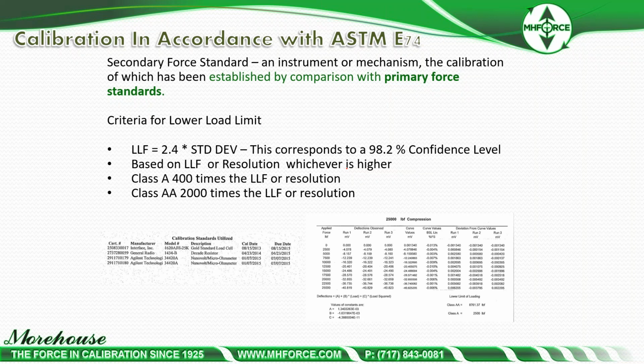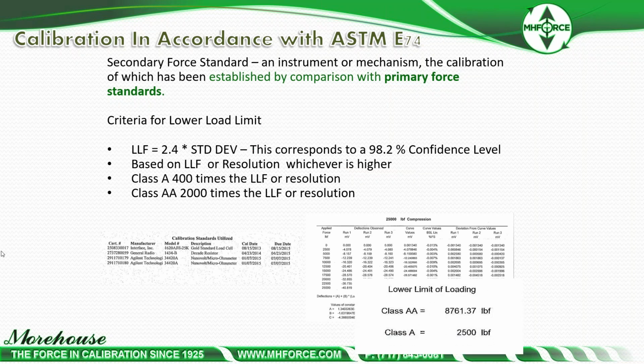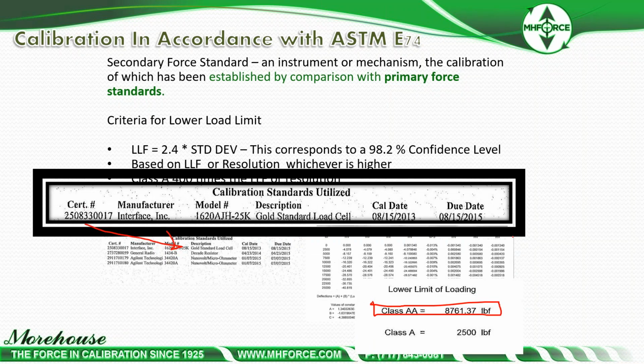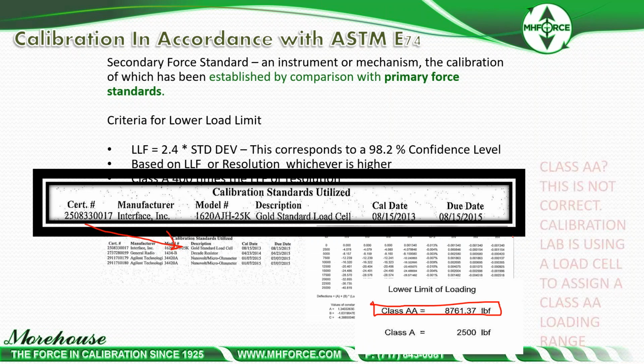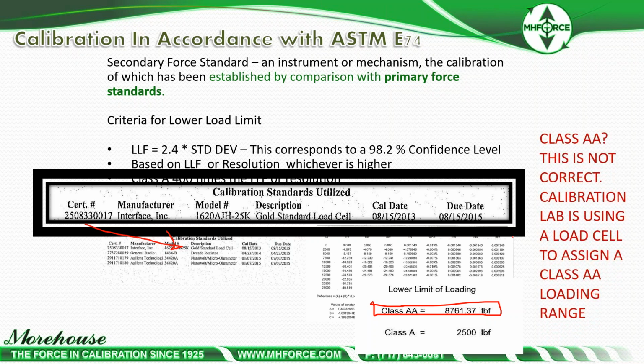This is just another example. Here we have a calibration standard. And if we look at this, what we really want to show is they're using secondary standard load cells and assigning a Class AA range. This should never happen. It's just not something you want. There again is the load cell that's happening. This is an older example, but it still happens. So this is not right: a calibration lab is using a load cell. You cannot assign Class AA with a load cell, ever. So check that. Check your cert, check the scope of the lab. If the lab does not have primary standards, they cannot assign a Class AA loading range.